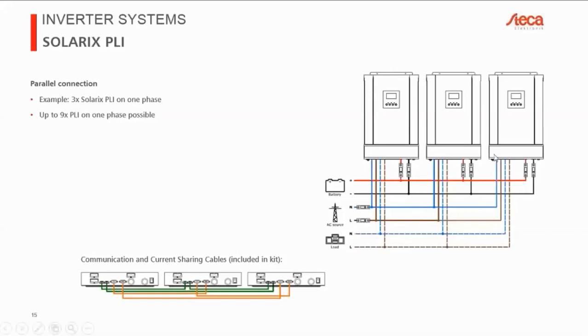But because we're using 3 inverters on a single phase, we need to make sure that the power that we require is distributed evenly across all the inverters. Because otherwise what would happen is one inverter would maybe be delivering 5 kilowatts and the other 2, 1 kilowatt. And that means that that single inverter will go into overload much more quickly than the others will. So it's important to keep all the inverters which are in parallel on one phase running at the same power level. So that's what the cables in green here do. Those are the current sharing cables. So every time you have more than one SOLARIX PLI on a single phase interconnected, you need to use these current sharing cables which are included in the parallel kit.